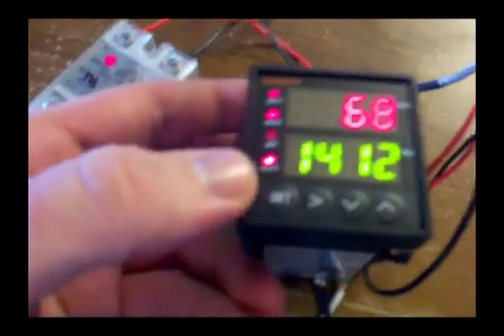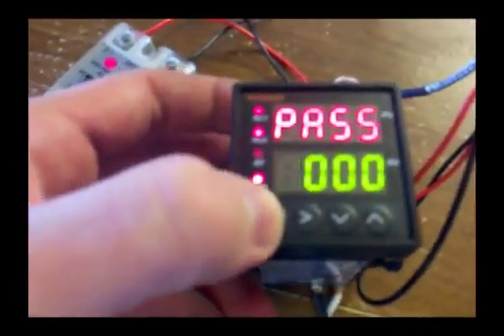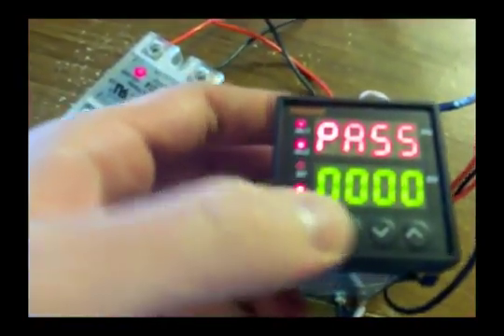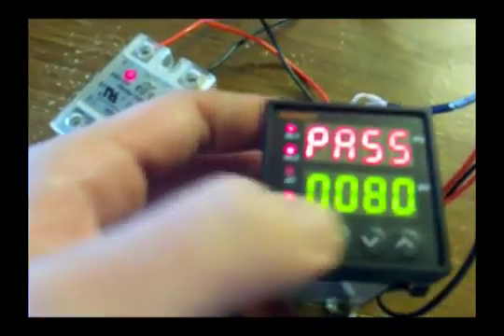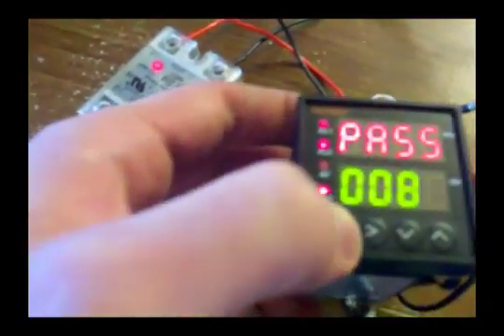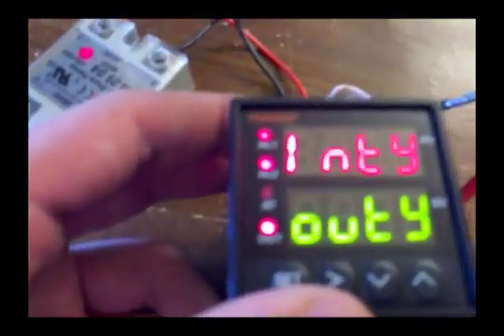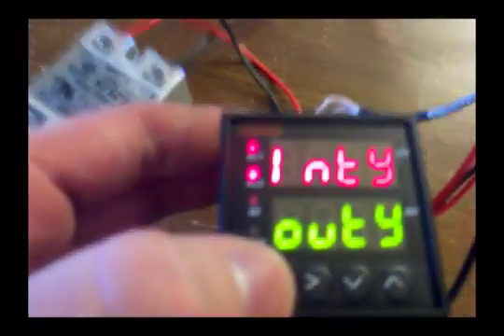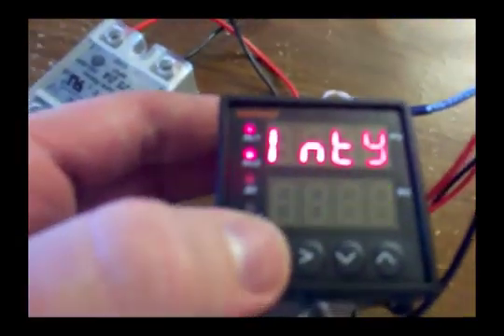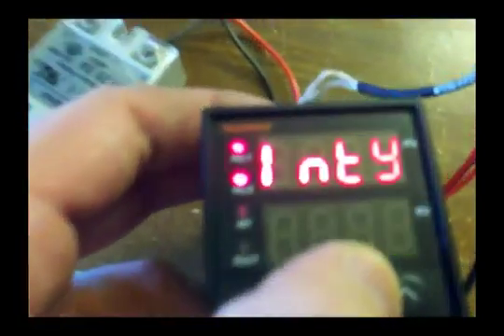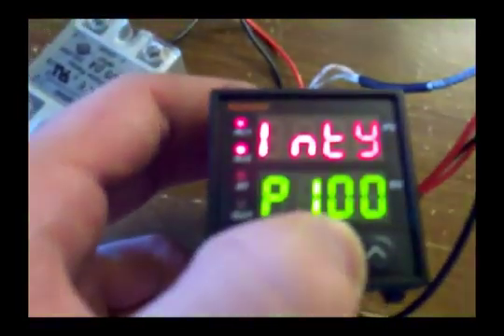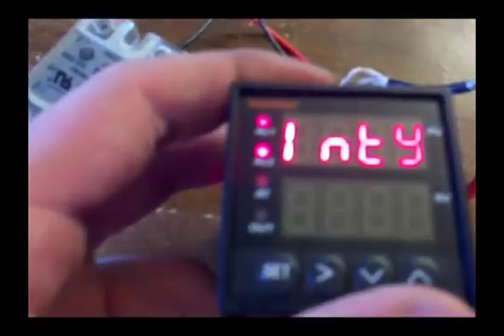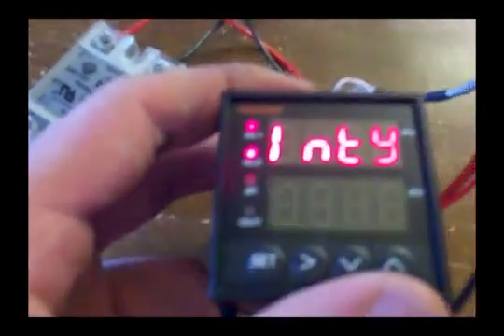and pass stands for password. There's a PDF document that I found that says that the password was 008. Put that in and press set. NT, that stands for in temperature, that's going to be your range of temperatures you select. So I press select, and these character codes here don't really mean anything. You have to reference it against the PDF document. P10.0, that's the setting it came on when I got it.